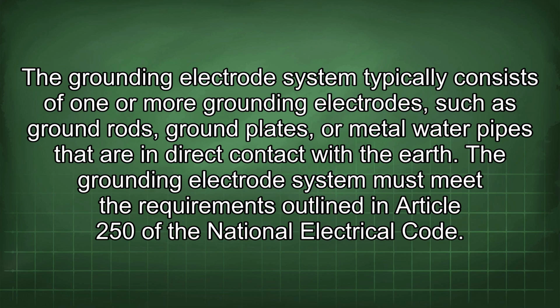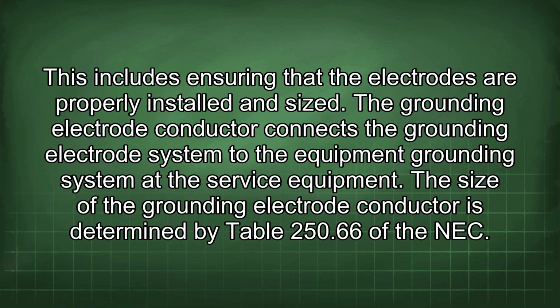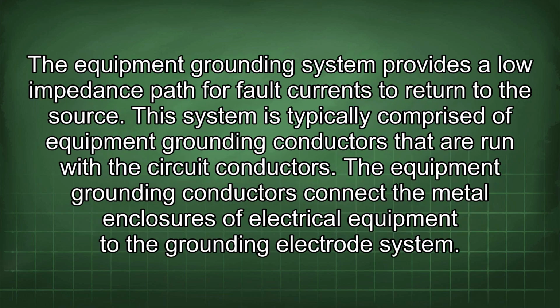The grounding electrode system typically consists of one or more grounding electrodes, such as ground rods, ground plates, or metal water pipes that are in direct contact with the earth. The grounding electrode system must meet the requirements outlined in Article 250 of the National Electrical Code. This includes ensuring that the electrodes are properly installed and sized. The grounding electrode conductor connects the grounding electrode system to the equipment grounding system at the service equipment. The size of the grounding electrode conductor is determined by Table 250.66 of the NEC.